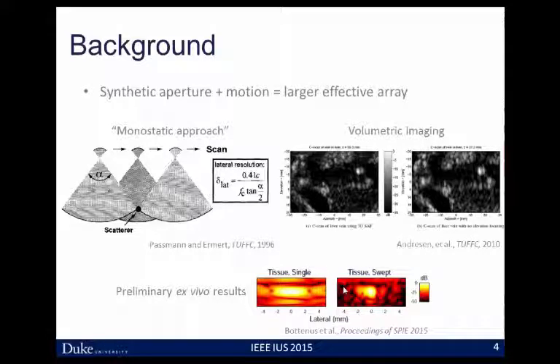The method we'll use is synthetic aperture imaging. The literature has a long history of using synthetic aperture imaging with transducer motion to build up larger effective arrays. The simplest approach is to use a single element — the monostatic approach — both in transmit and receive, moving that single element around to build up an effective array. If we start with an array, we can do volumetric imaging, sweeping the array out of plane to build up an effective volumetric transducer. Our proposal here is to move that array not out of plane, but within the imaging plane, building up an effectively larger array. From our preliminary ex vivo results, we expect to see greatly improved lateral resolution.